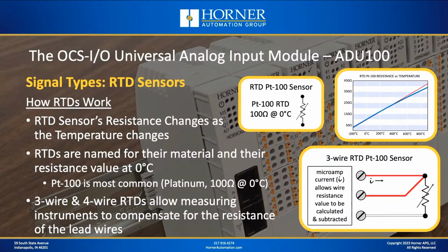Now, the most common RTD sensor type is a PT100. PT stands for platinum because that's the material of construction, and the 100 means that the reading for a PT100 at 0 degrees Celsius will be 100 ohms. Now, 100 ohms is a relatively low resistance value. And if you have a significant amount of wiring between your measuring instrument, like the ADU100, and your temperature probe, then you might have a few ohms of resistance in your lead wiring. And a few ohms of resistance, if it's not compensated for, will cause an error in the reading.